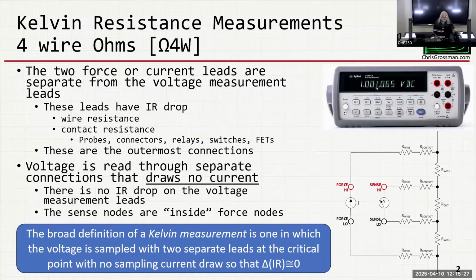So generally, if you're measuring anything on the order of 100 ohms or smaller, and you want an accurate measurement, you need to go to a Kelvin measurement. This is called a 4-wire ohms measurement.